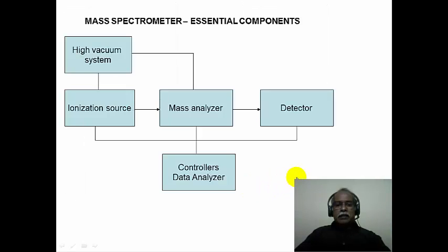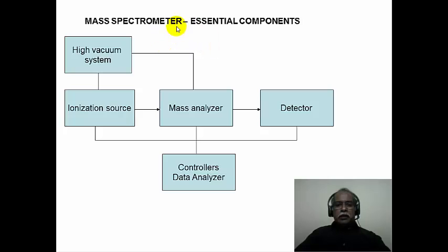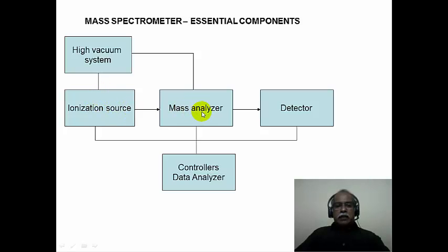A mass spectrometer essentially consists of five components. First, a high vacuum system, because mass spectrometry deals with ions generated in the gas phase. A vacuum of the order of 10⁻⁶ to 10⁻⁹ torr is required. Then there is an ionization source — depending on the technique, different ionization sources are involved. The ions generated in the ionization source are fed into the mass analyzer.